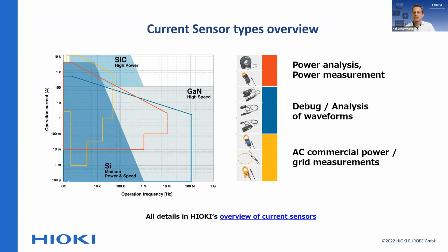On the other side, you see the ones typically used for debug and analysis of waveforms. That's the blue one. They're high bandwidth sensors, going up to 100 megahertz, and down to the smallest currents of 100 microamps, not even milliamps but microamps. So they go very, very low in current.